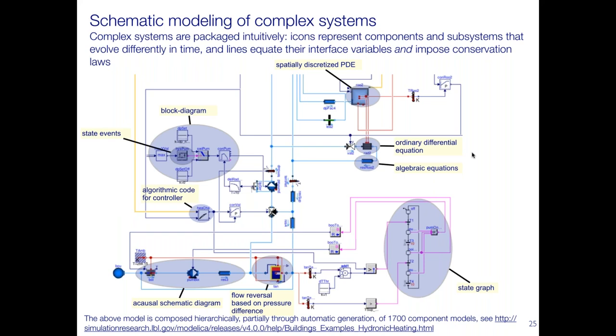You can do block diagram modeling using the signal flow chart shown before, which is well suited for control sequences. You can have blocks for state events—for example, this switch outputs true or false whenever the input, here the room air temperature, crosses the threshold. On the top right is the spatially discretized partial differential equation for a room model.